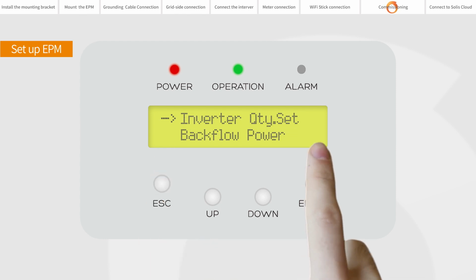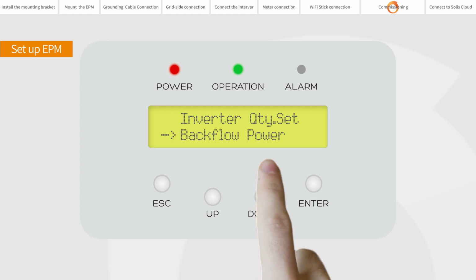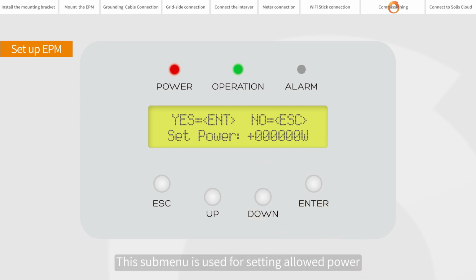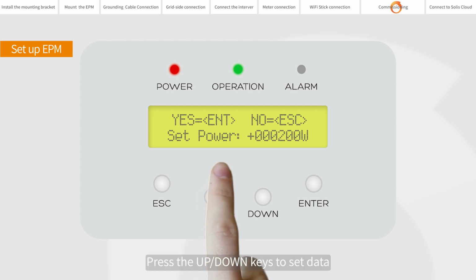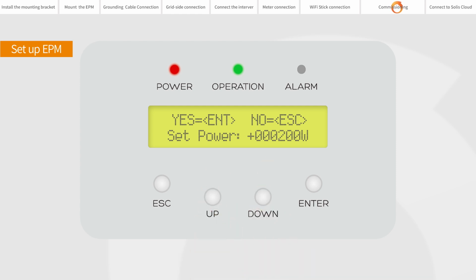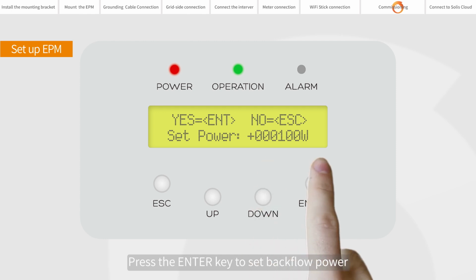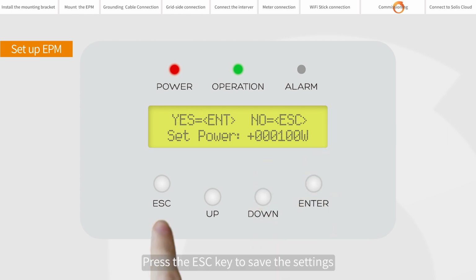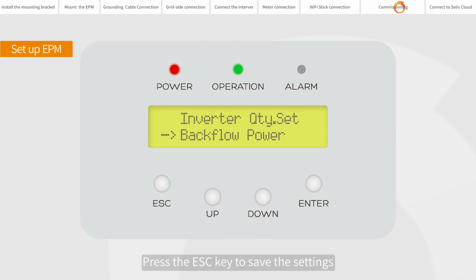Advanced settings. Backflow power. This submenu is used for setting allowed power that inverter can generate to grid. Press the up or down keys to set data. Press the Enter key to set backflow power. Press the ESC key to save the settings and return to the previous menu.